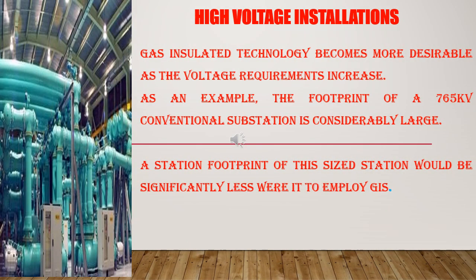High voltage installations. Gas insulated technology becomes more desirable as the voltage requirements increase. As an example, the footprint of a 765 kV conventional substation is considerably large. A station footprint of this size is significantly less were it to employ GIS.